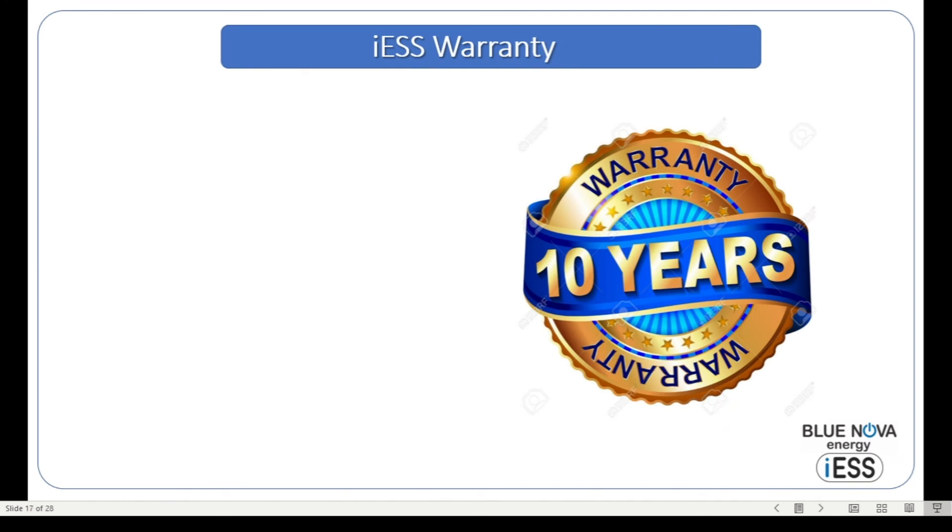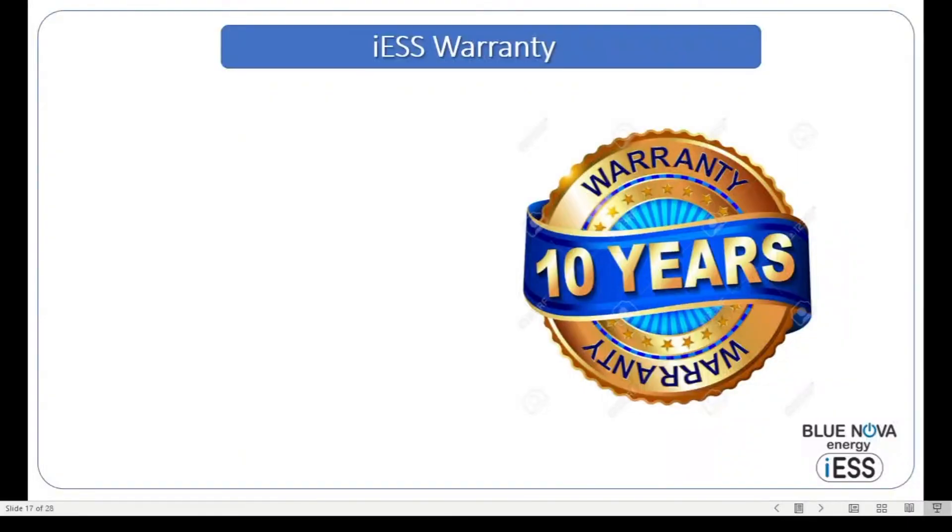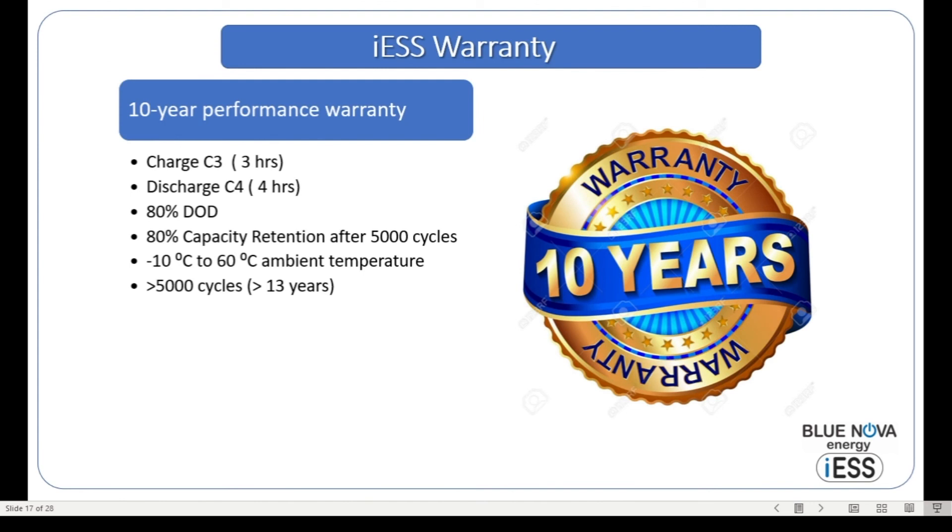Let's look at the iESS warranty. We're offering a 10-year performance warranty — unlike most warranties, which are workmanship warranties. What we are saying is that if you charge the battery typically in three hours, discharge it in four hours — although the typical discharge would be at night, a 10 to 14 hour discharge — and you discharge it to 80% depth of discharge on a daily basis, operating between minus 10 and 60 degrees Celsius, the battery system will retain more than 80% of its initial capacity after 5,000 cycles. More than 80% will be retained after 13 years, and we can guarantee this capacity retention after 10 years.